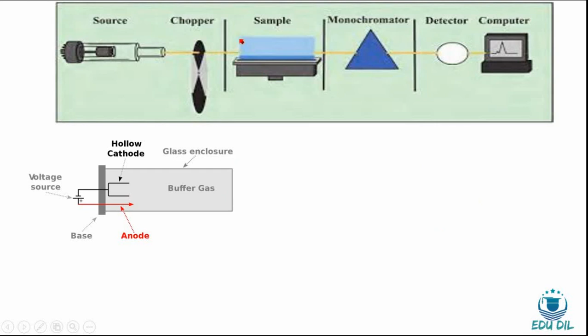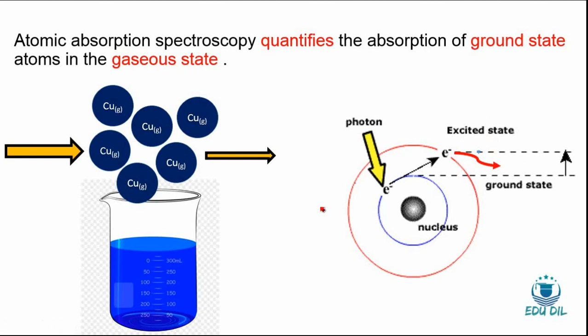That means the beam of radiation emitted from the hollow cathode lamp goes through a chopper. What does the chopper do? It chops, that means it breaks this beam of radiation. Why is that? It prevents the formation of a steady beam of radiation and forms pulsed radiation. Why? As I mentioned in the previous picture, the sample absorbs some amount of energy and goes into an excited state, but it isn't stable there. It also has to come back to its ground state, and during that it emits some amount of radiation. So not only does it absorb, it also emits radiation, so it is very difficult to detect the real amount of energy absorbed by the sample, because not only absorption but also emission occurs.